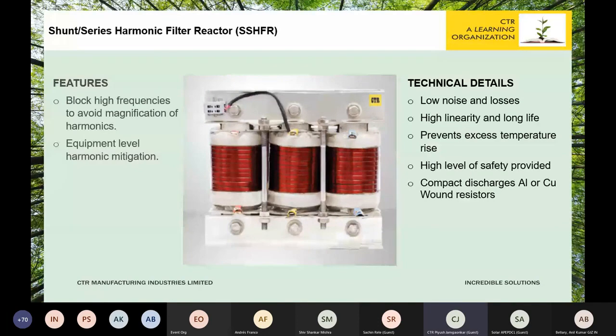This product is designed to have low noise and low losses, very high linearity and a very long life. The NC contact is provided for excess temperature rise. The standard range that we are offering is in low voltage with a tuning of 2 to 14%, and in medium voltage, that is above 6.6 kV, with tuning from 6 to 12%.